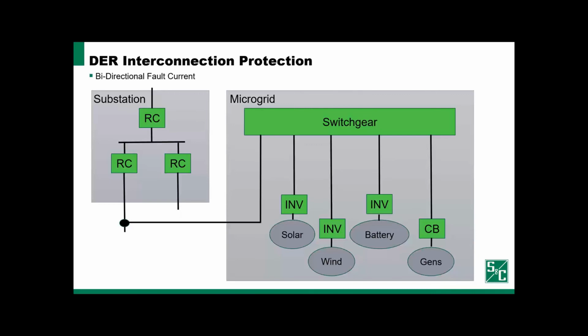Now, in this system, let's look at what happens with faults at different locations. If we have a fault over near the generators on the far right, you can see that fault current is coming into the switchgear on the left and out of the switchgear on the right. Now, if the fault was instead on the tie line between the substation and the microgrid switchgear, we see fault current coming out of the switchgear on the left and in on the right, the exact opposite of what we just saw a moment ago.